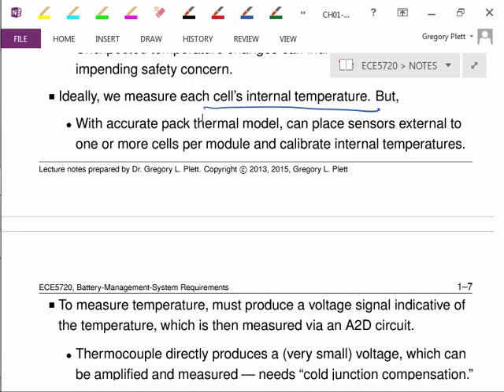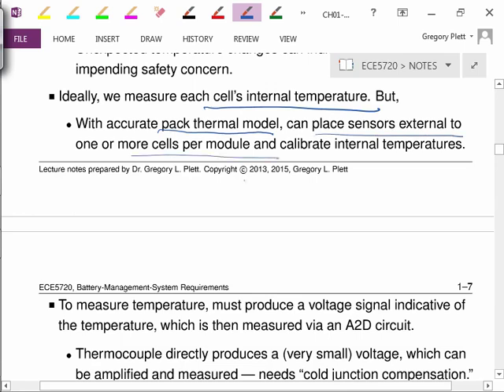So usually we measure temperature outside of a cell, sometimes right at the surface, sometimes not. We saw the linear technology voltage measurement part could measure up to 4 temperatures per 12 cells. That means we'd need a thermal model for a battery pack that converts temperature readings at one measurement point to predicted temperatures at different points inside the module or pack. So we place sensors external to one or more cells and calibrate the internal temperatures based on our model, and that turns out to work pretty well.